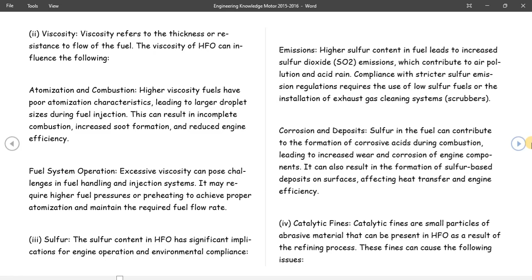And the next one is catalytic fines. Catalytic fines are small particles of abrasive materials that can be present in heavy fuel oil as a result of the refining process. These catalytic fines can cause issues, which are engine wear, as they can damage engine components. Next is filter plugging. Catalytic fines can clog fuel filters, reducing their effectiveness and leading to fuel starvation. So these catalytic fines can hang around the filter and may lead to the filter not working well.